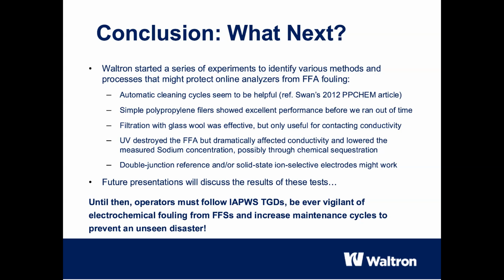Filtration with glass wool was effective for preventing adsorption onto contacting conductivity electrodes, but unfortunately introduced sodium into the sample. UV treatment can destroy FFAs, but also affects conductivity and appears to lower the measured sodium concentration, possibly through chemical sequestration. It merits further testing. Technological upgrades such as double-junction reference electrodes or solid-state ion-selective electrodes could also significantly improve the stability of sodium measuring devices. We will discuss the results of these tests in future presentations.